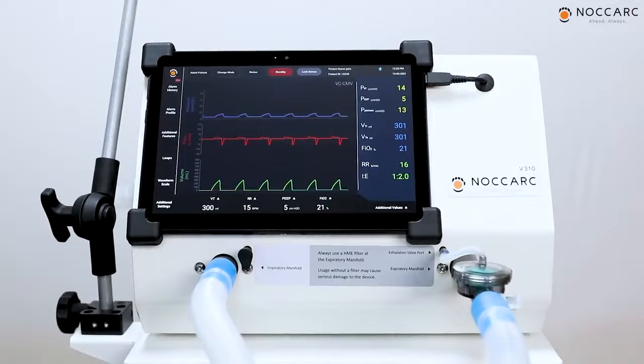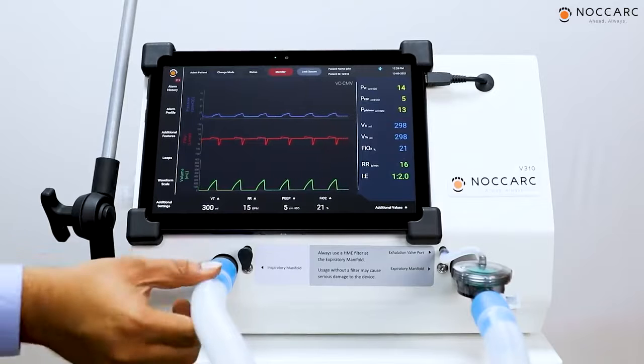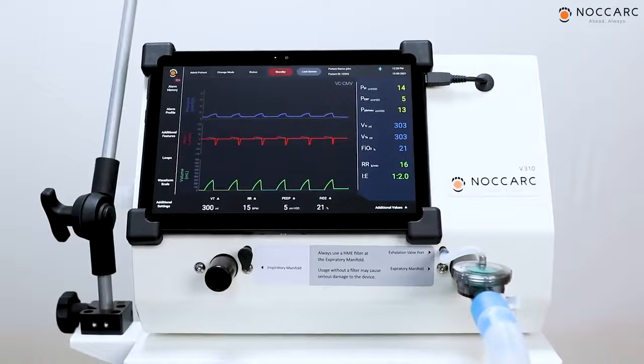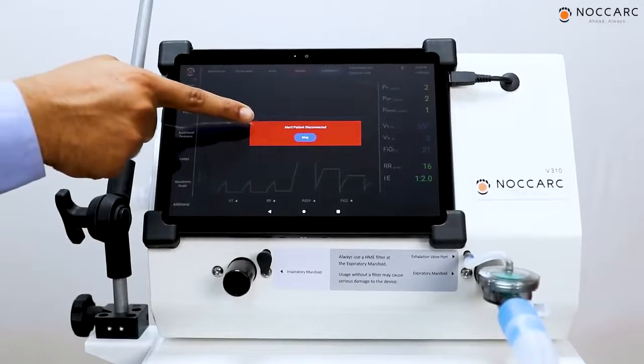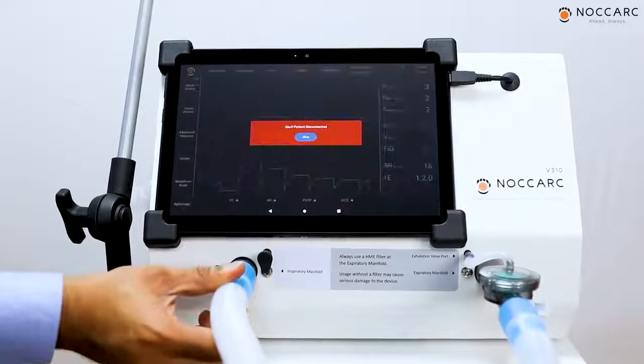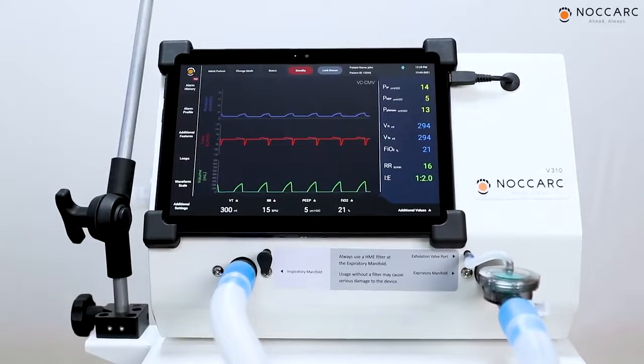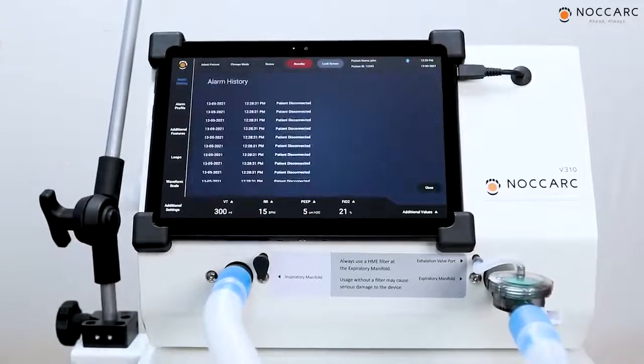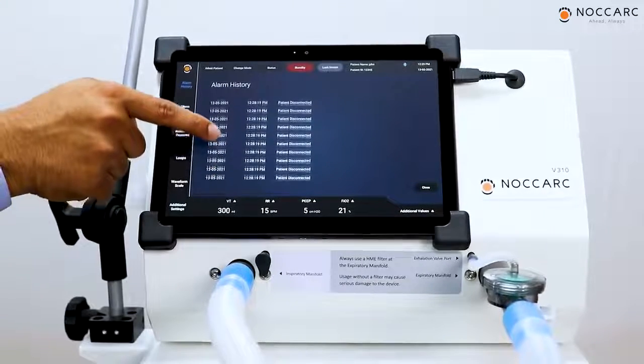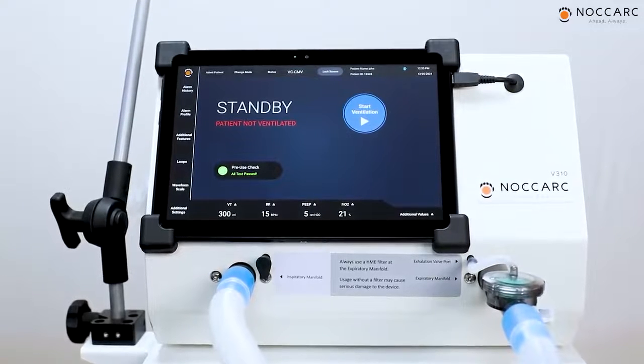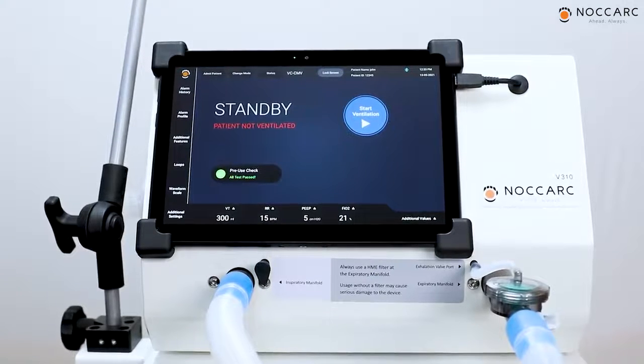To test patient disconnected alarm, I will simulate the condition by removing the patient tube from inspiratory port. Here you can see patient disconnected alarm is showing on the screen. When patient is restored, by closing the loop between inspiratory to expiratory port, it will show VTI and VTE properly, that ensures the patient is properly connected and ventilation is proper. You can check the alarm history to see what are the alarms given by the ventilator. Whenever any alarm comes on the screen, yellow color indicates warning alarm and red color indicates danger alarm.